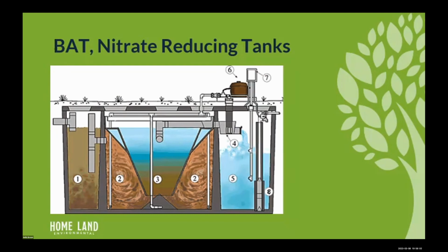All right, good. So we have this first chamber here, which we call the trash tank now, right? It's very small. This may be 200 gallons of capacity. And as we know, there's not a whole lot of retention time. That water is going to go in and out. Bacteria is not going to eat it up. What's the point of that? Well, we call it a trash tank. We wanted to collect the big stuff. And I'm not going to get graphic because we just ate dinner. But we want kind of dirty water to pass through, but we don't want it to be too heavy, right? There's no retention time, blah, blah, blah. It gets into the second chamber.